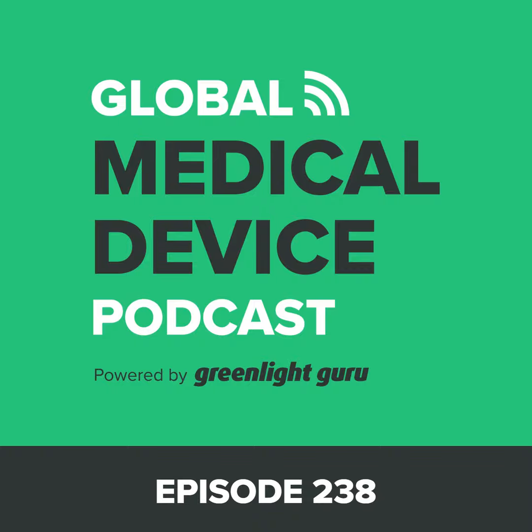The first one is it can't be intended to acquire, process, or analyze a medical image or a signal from an in vitro diagnostic. That's clearly software as a medical device. Yes, absolutely. So that's a good thing. The second thing, it's intended for the purposes of displaying, analyzing, or printing medical information about a patient or other medical information, such as peer-reviewed clinical studies and so on. So that one is another boundary.